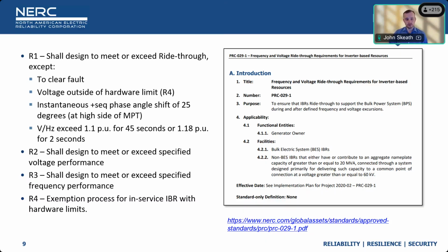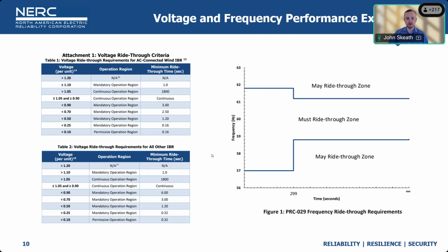So R2 is the follow-up of R1 that defines the exact voltage ride-through expectations. So the owner of the IBR shall design or meet those voltage performance markers, and I have a chart on the next slide to really show what they are. And R3 is the frequency counterpart that says you shall design or meet or exceed the specified frequency performance. And I believe there's just a very limited subset that is a broad application. R4 is that exemption process for in-service IBRs with hardware limits. So let's take a look at the voltage and frequency curves.